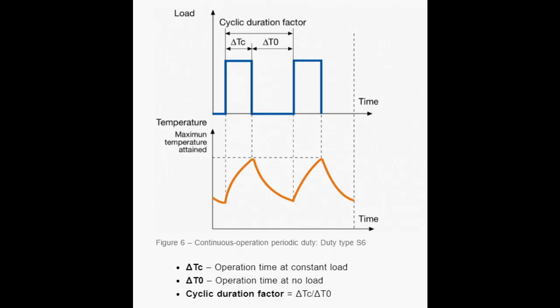In S6, we have a time of operation at constant load and a time of operation at no load. There is no time de-energized and at rest. We have load, we have no load, but the machine is always in on condition.